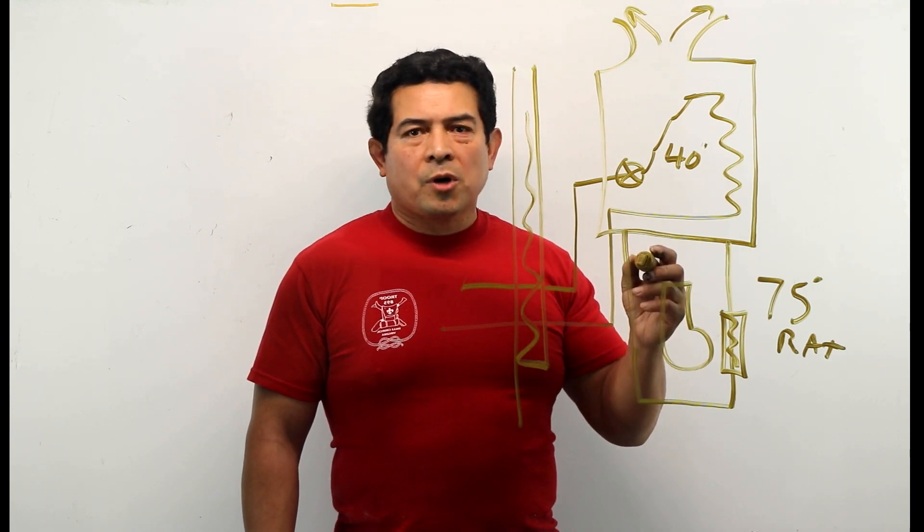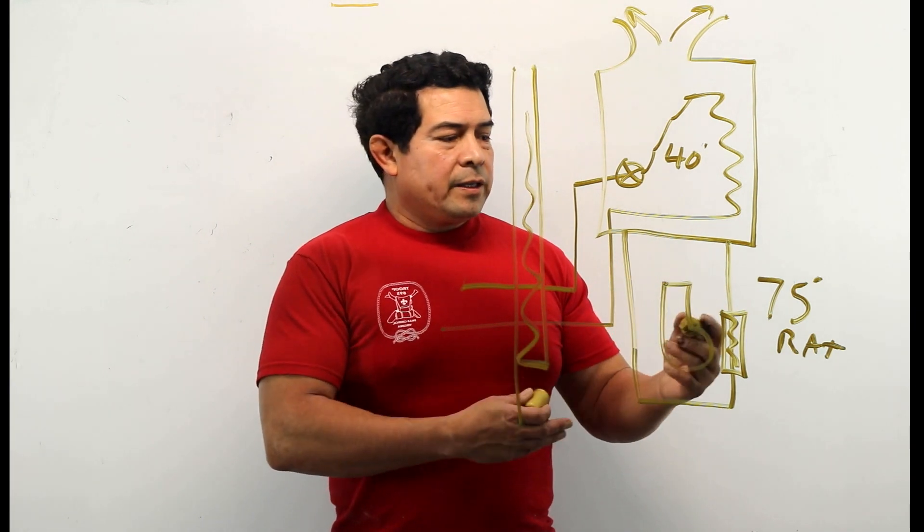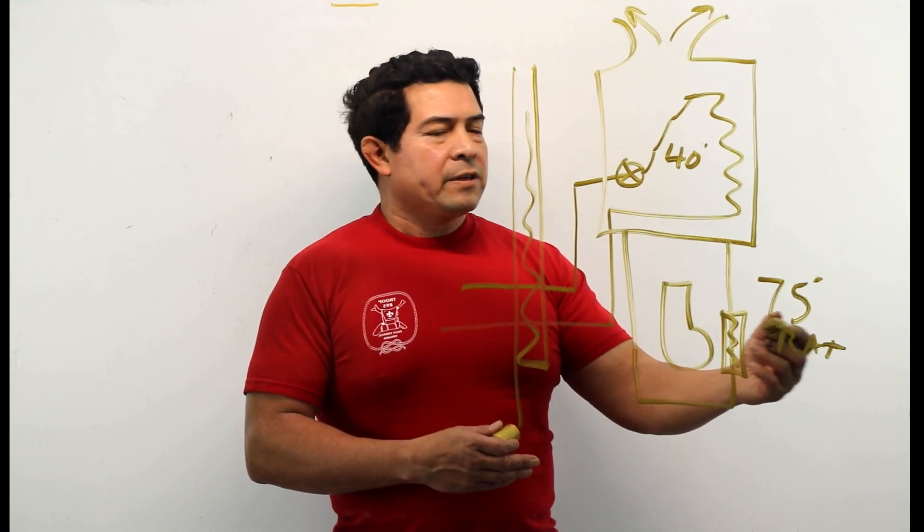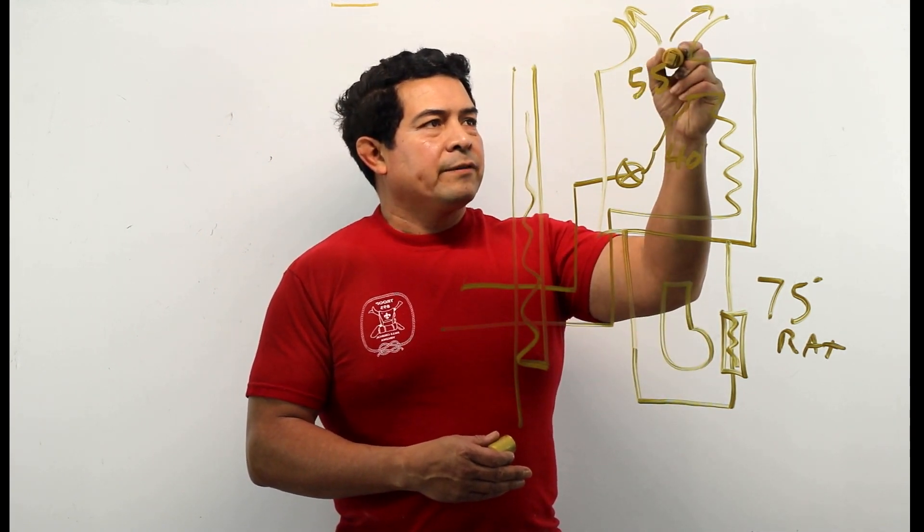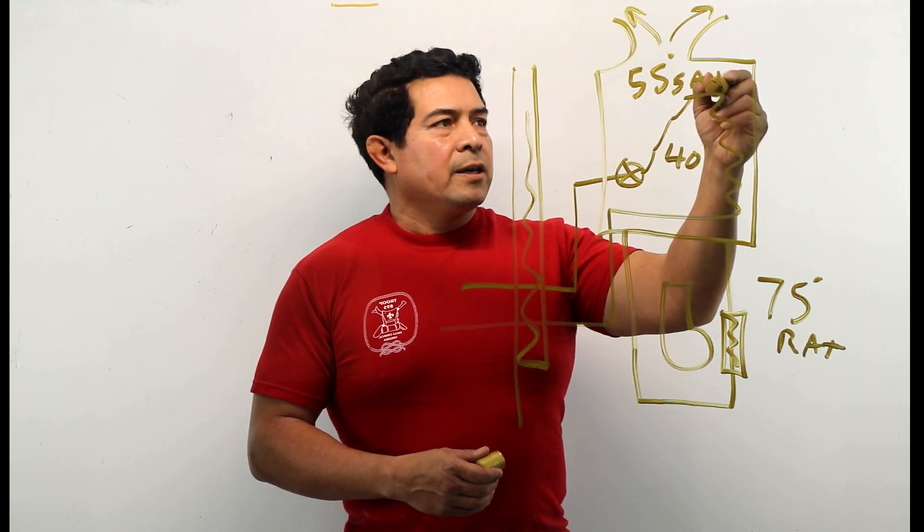But if the system is charged properly, if the system has been running for a while and it's working like it's supposed to, then what you're going to have is 75 degree air coming in and approximately 55 degree air going out. That's going to be your supply air temperature.